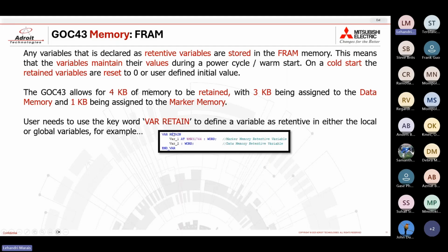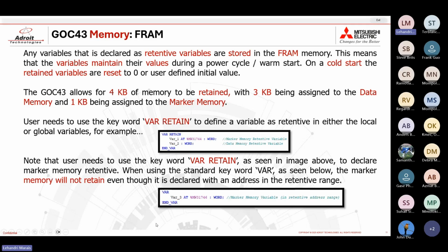So important thing to note, for the marker memory to be retentive, you need to both declare it using the keyword retain as well as declare it in the range of the retentive memory, so that range we mentioned previously.